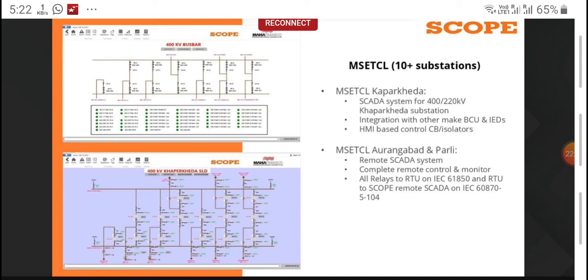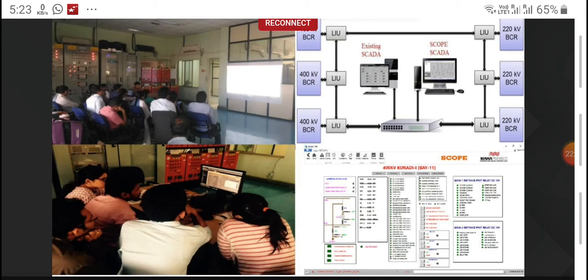So they came up with one tender called independent or third-party SCADA solution, where there are many manufacturers' relays, like ABB relays, BCUs, even Siemens, and some other renewable OEM relays. Now, what we did in this case, you can see this picture. You can see that we have not disturbed any existing system. The 400 kV network is the same, and we have not changed any single relay, because earlier the OEM was recommending changing the relays and the entire system to make the SCADA system or automation system work.